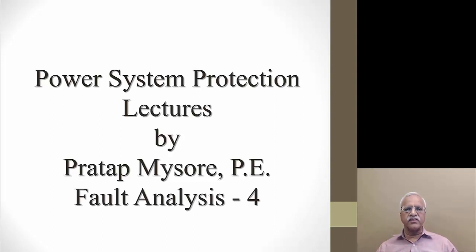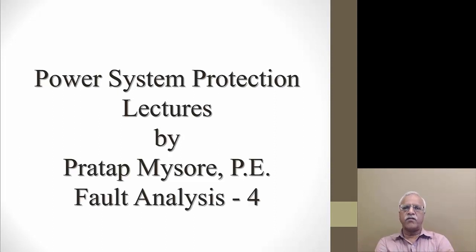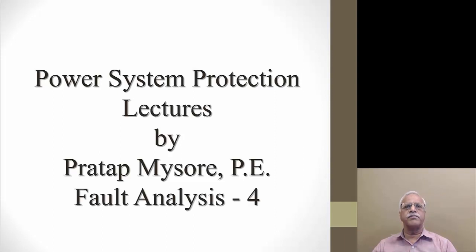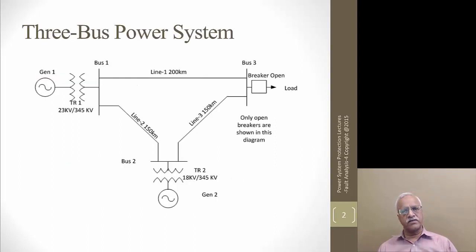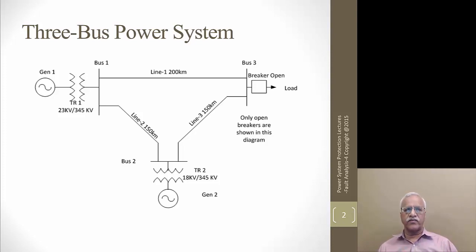In actual conditions, we don't do this manually. We simulate or model everything in a short circuit program, which takes care of calculating and providing us with the short circuit values, voltages, and currents at different locations. This is just to give you a concept. We'll go through a simple three-bus system which has two generators: one generating at 23 kV, the second at 18 kV, stepped up to 345 kV to transfer power from the generating side to the load side.